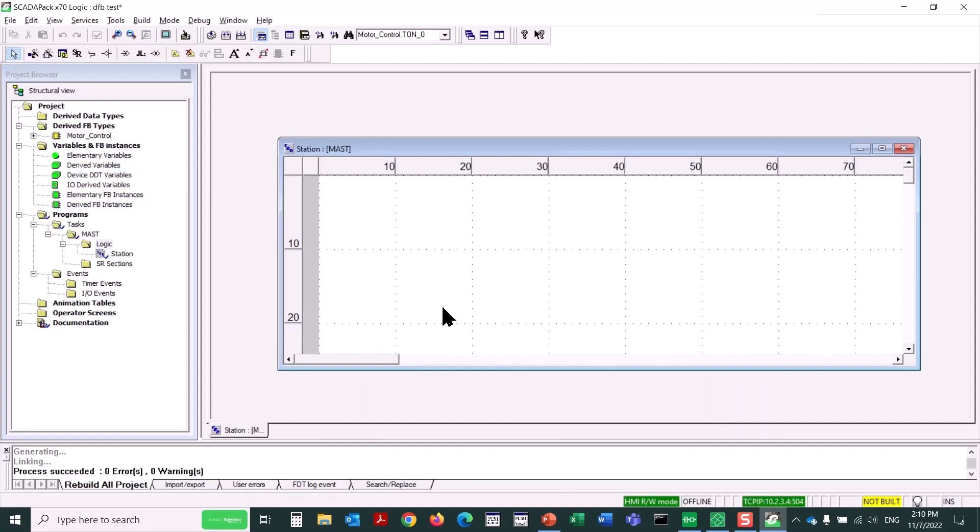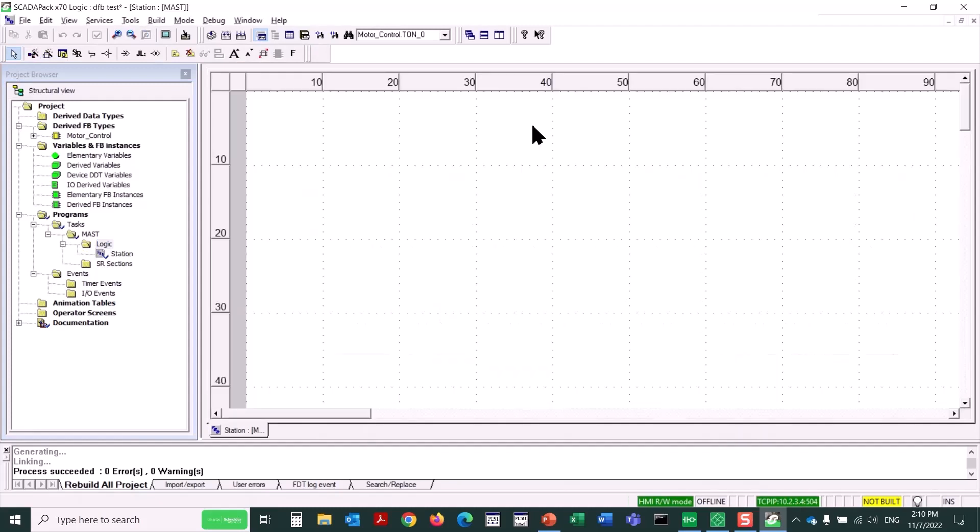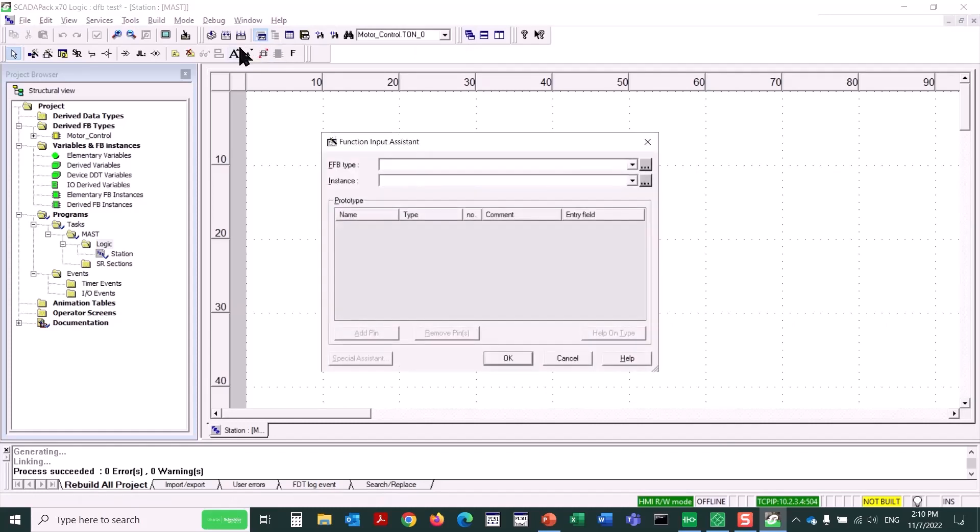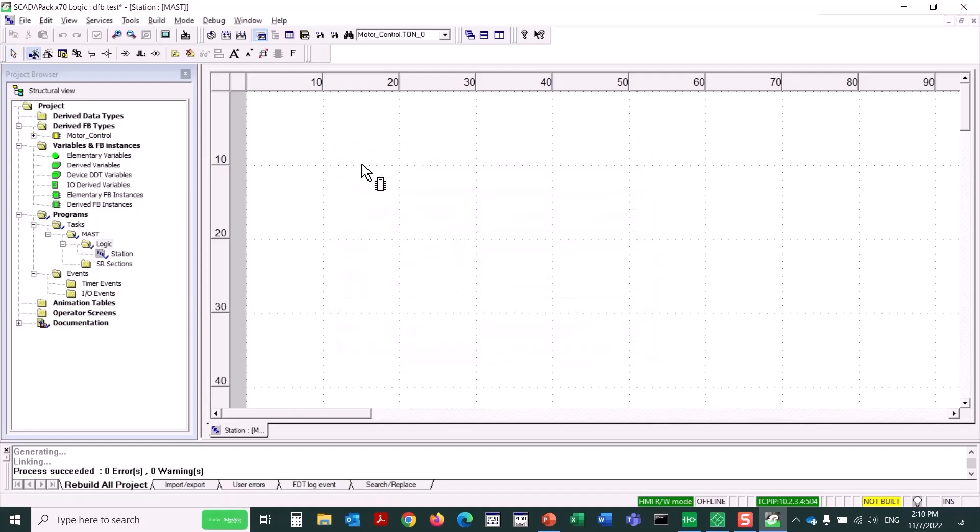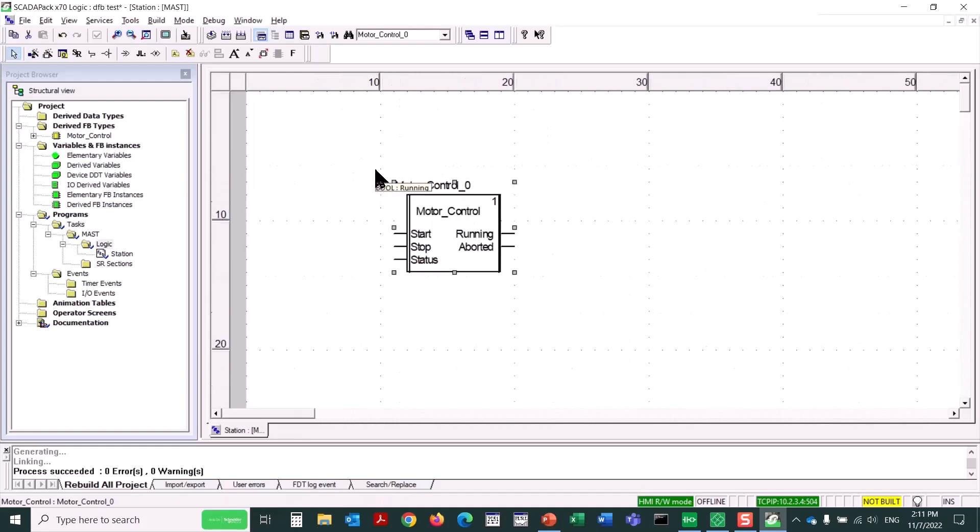Now we could use the Input Assistant button again, or we could just press Control-I. And now I can use the Ellipsis button to find the custom function block I created, the derived function block. Or I could just type Motor Control, and it should automatically populate. There it is. So I'll click OK. And then I just click where I want to drop this function block. There it is. I can press the Control key and use my mouse's scroll wheel to zoom in, if desired.